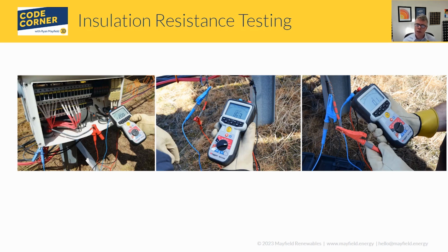There might not be, depending on the exact voltage you're using, what that reading is coming back at, and what the allowances are. The other 2 on the bookends: greater than 200 gigaohms, that's a huge resistance. And 0.1 kilohms means there's essentially no resistance, so there's a problem in that one. Understanding the meters is important, but these are just different types of readings that you may see out in the field.